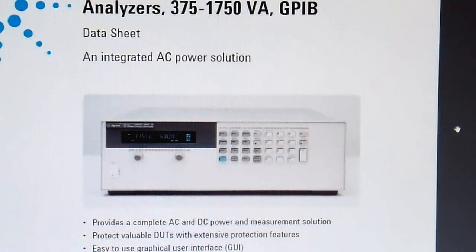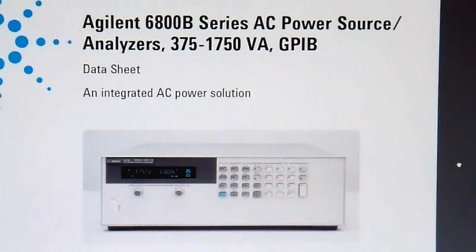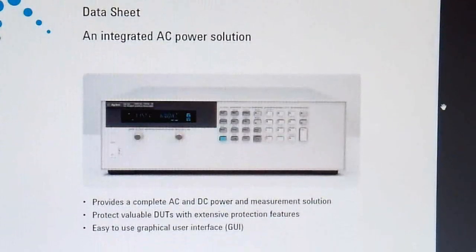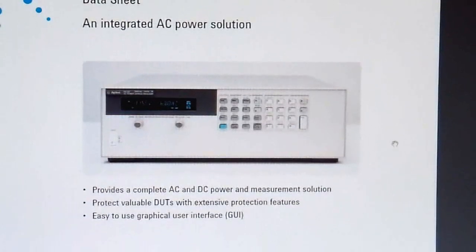There are digital solutions to it too. This is a power source from Agilent. This is especially popular in lower wattage units, below 10 kilowatts typically. But these are nice because they're programmable. You can program the frequency and the voltage and, among other things.